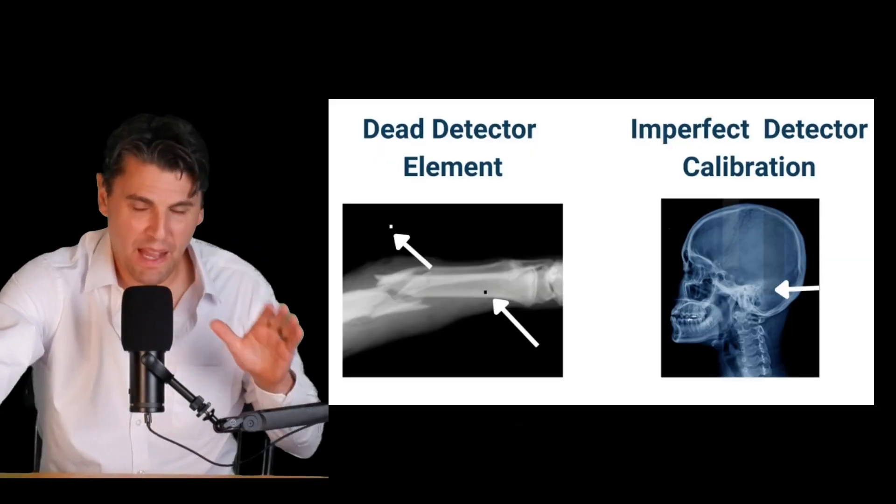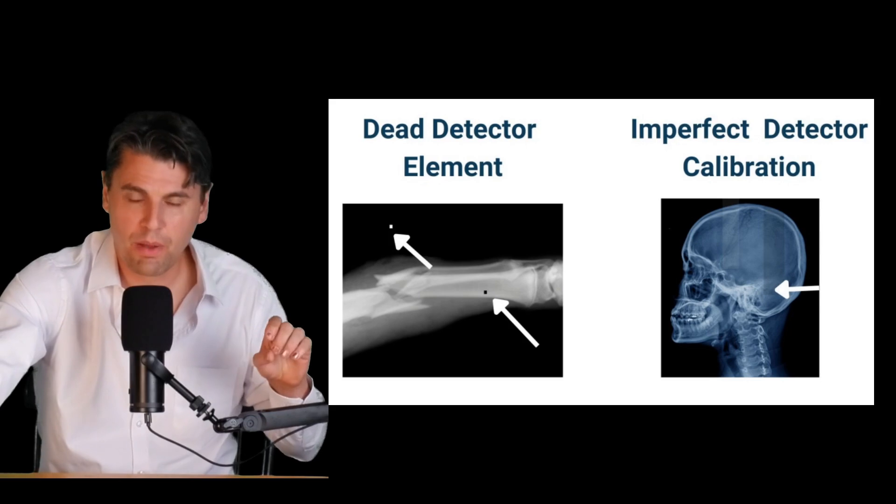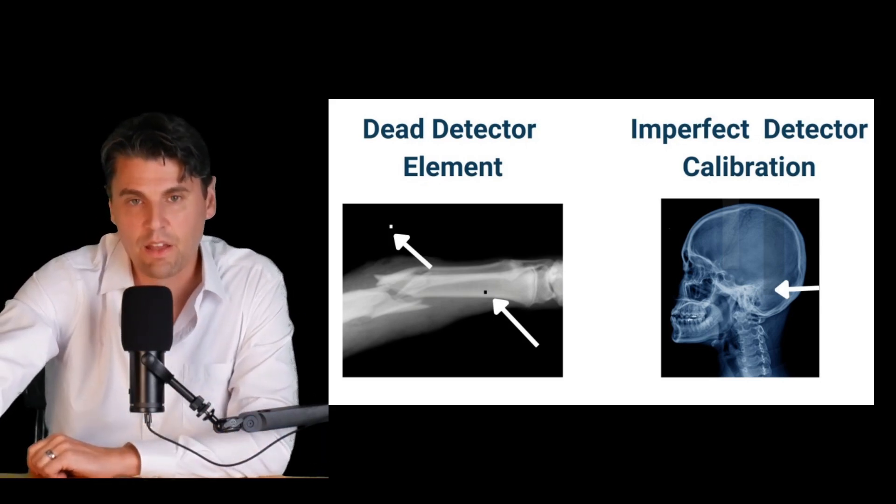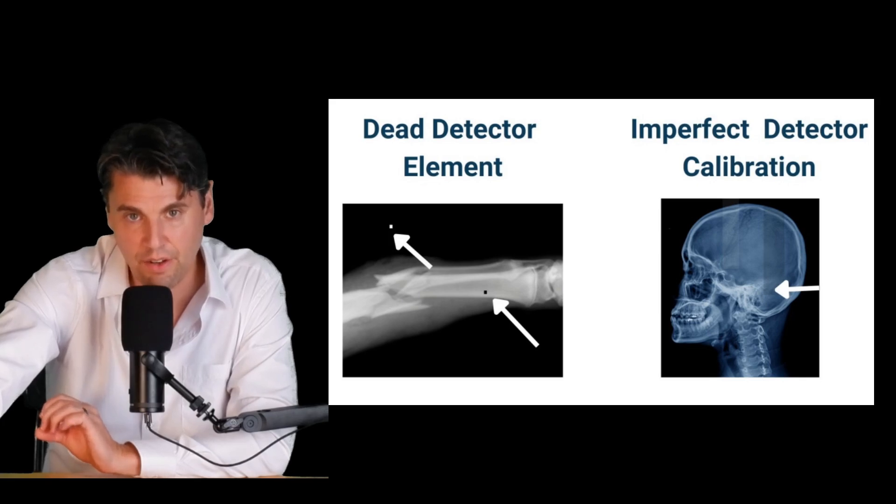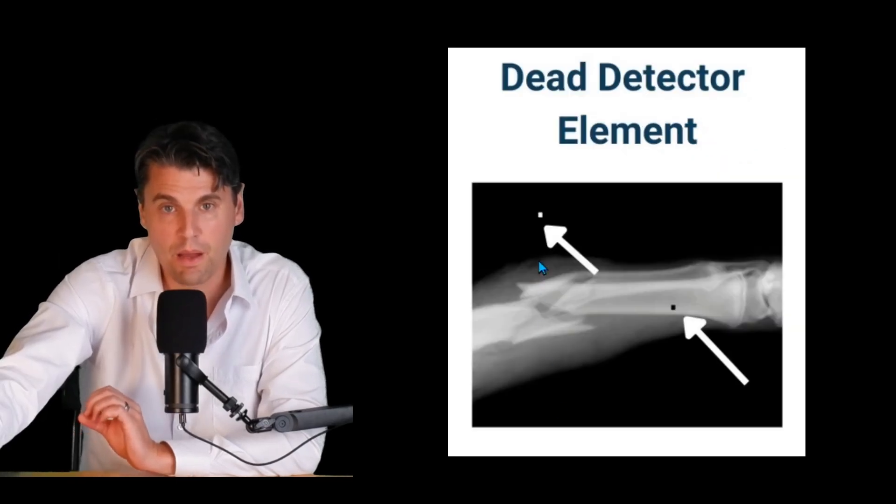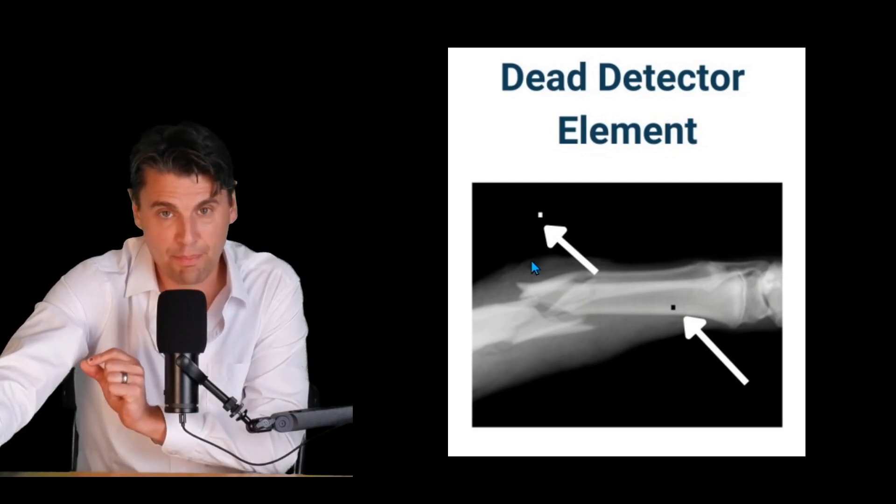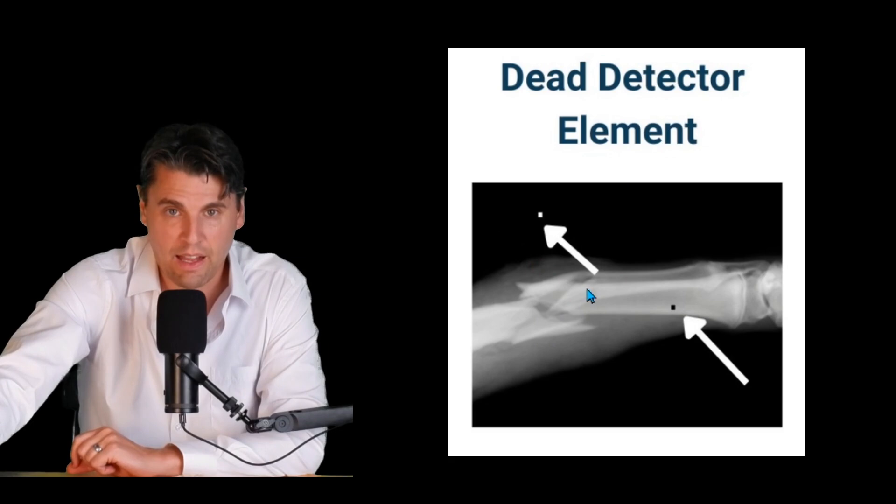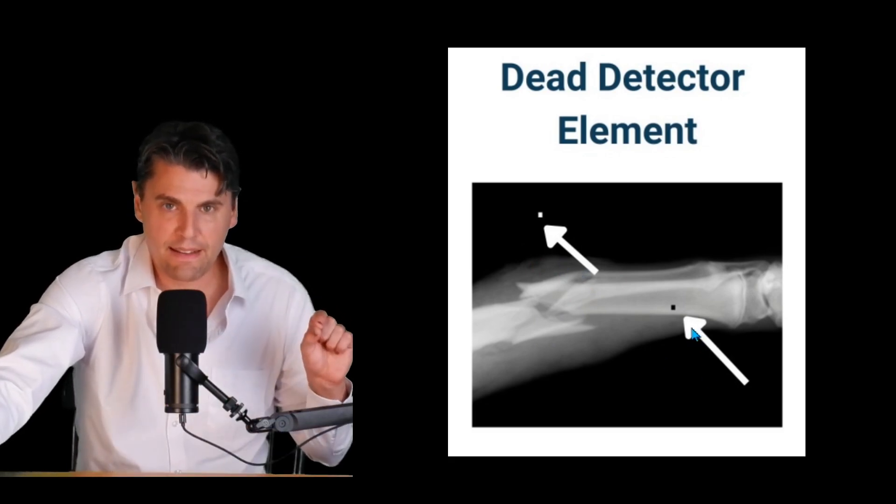From the perspective of the digital system there are corrections that are used and in the case that there's changes to the detector it's possible that there can be essentially bad pixels or bad detector elements that are not properly accounted for in the calibration. This can lead to kind of spurious bad detector elements.